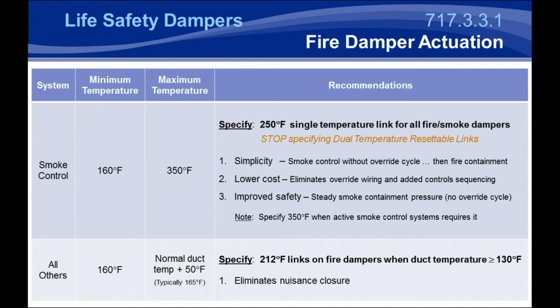So basically, for all your typical dampers that have been in the code for quite some time, they need to close within 50 degrees of normal duct operating temperature. So your fusible link then would typically be set to 165 degrees. Now, most traditional fire dampers do use fusible links, and these links are basically two pieces of metal held together with a eutectic solder. That will soften and let the links separate when you get to a certain temperature rating. Unfortunately, these are not as accurate as, say, a bimetallic strip or thermal disc used in thermostats typically, or in the actuation of fire smoke dampers.